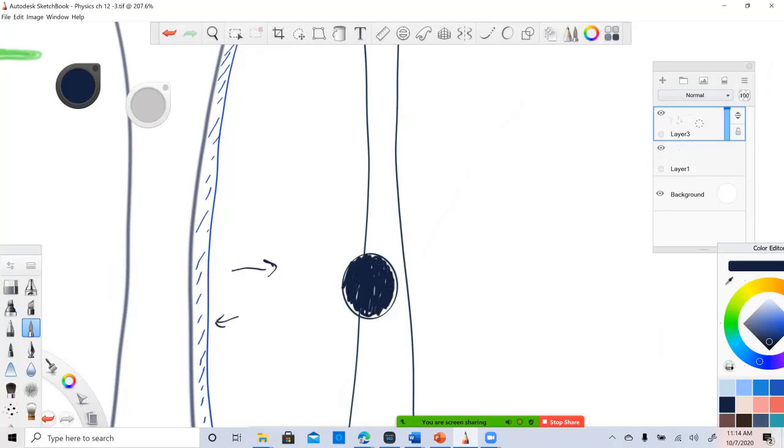I think it's the third dimension that I'm having a hard time describing. Okay, so there's our hypoechoic vessel, hypoechoic cyst, and the beam is, for the most part, aimed right at it. Only there's a bit of a problem here: part of that beam is not in the cyst. Part of that beam, the dimension we don't think about, the thickness dimension, is actually hitting the walls of the cyst or the walls of the blood vessel, either way.